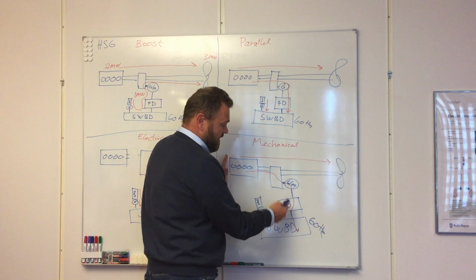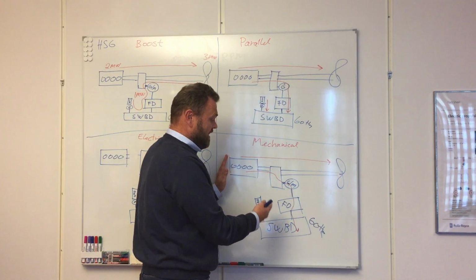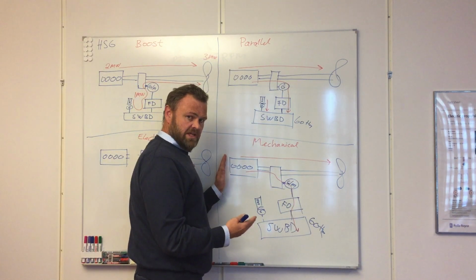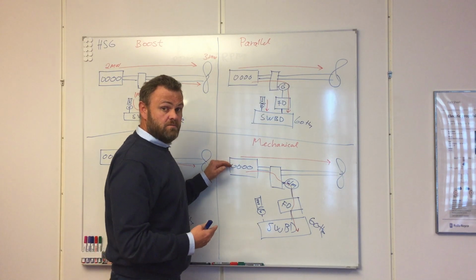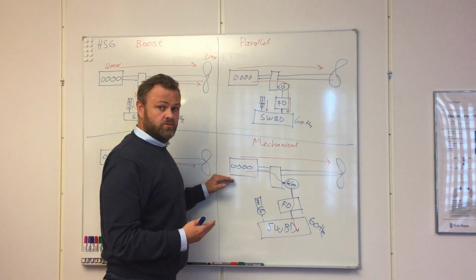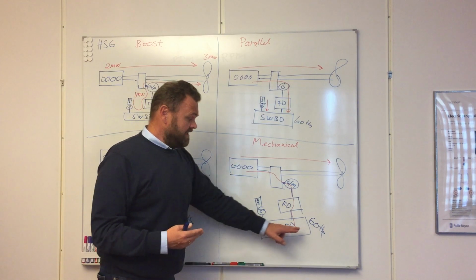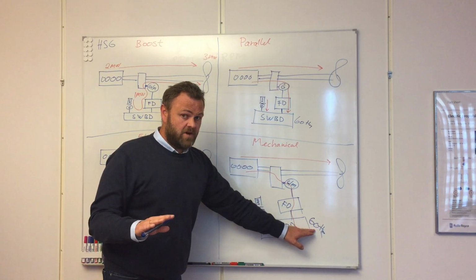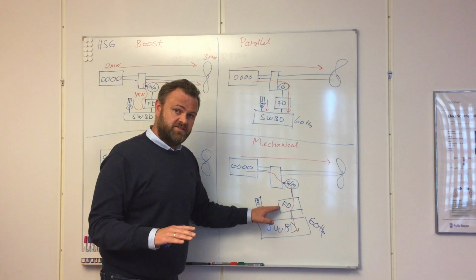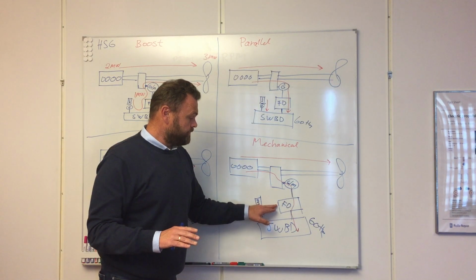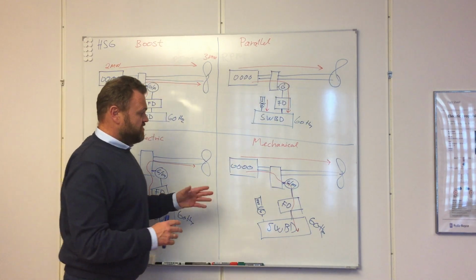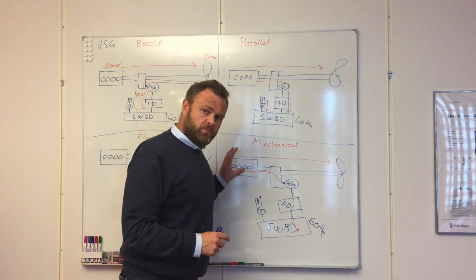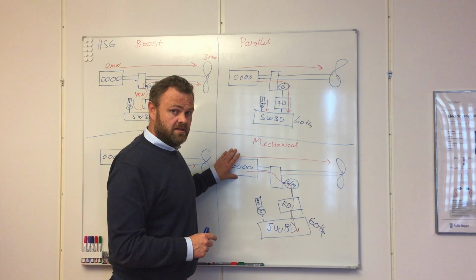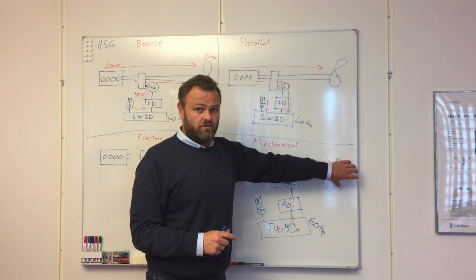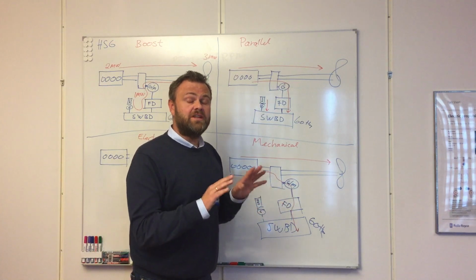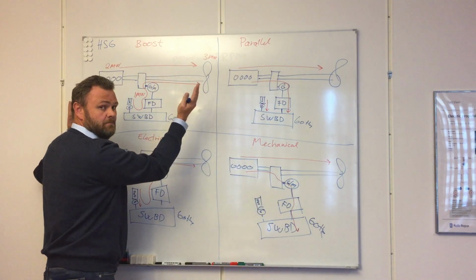However, with this frequency drive HSG setup, we give the system the possibility to take down the RPM from the maximum all the way down to idling, still making 60 Hz stable frequency on the switchboard, because we have this active front-end frequency drive in between. So with this solution you will have a more optimum utilization of the engine and the propeller in conditions where you do not need absolutely full maximum power.